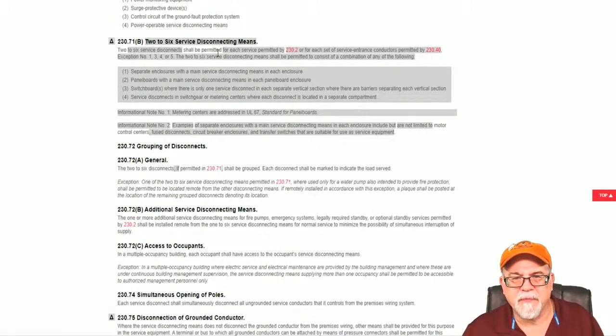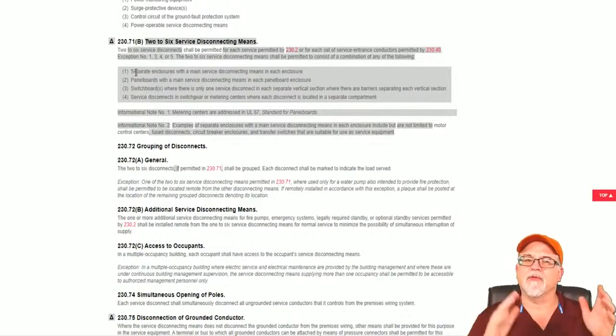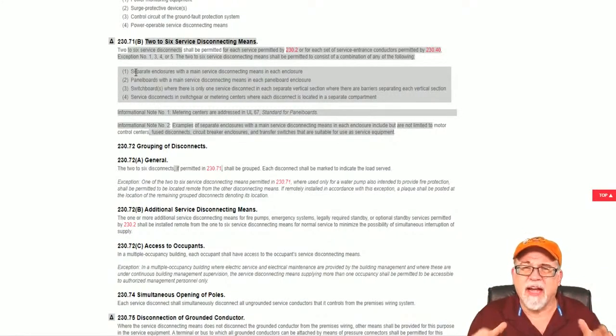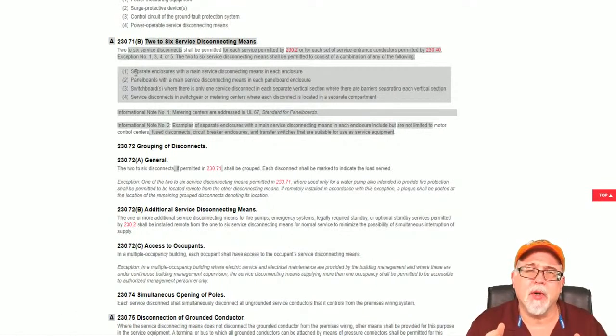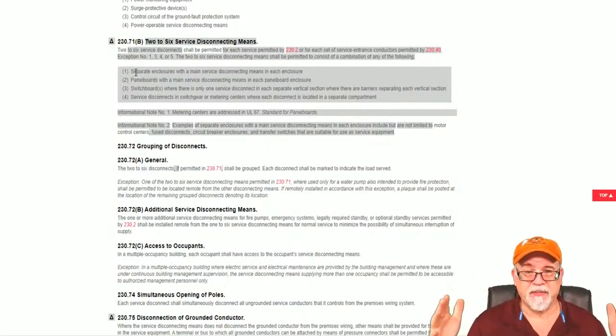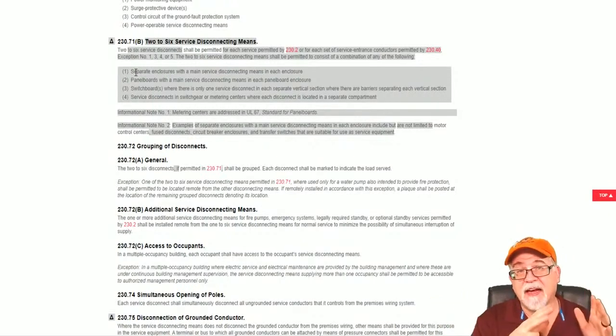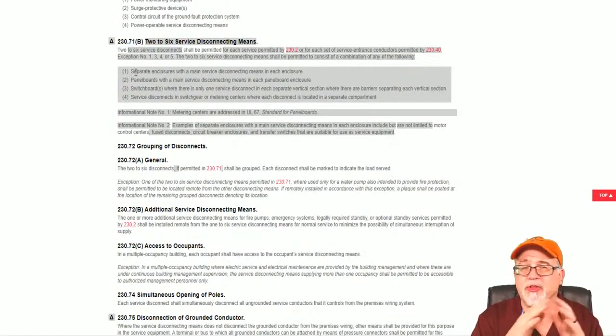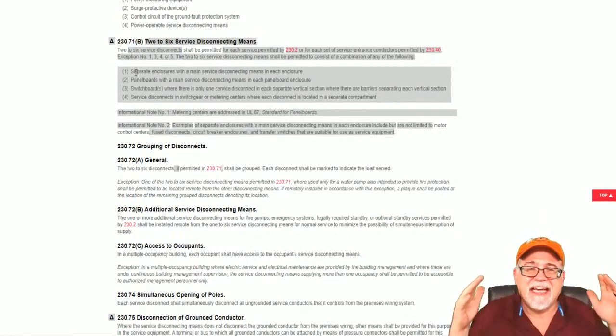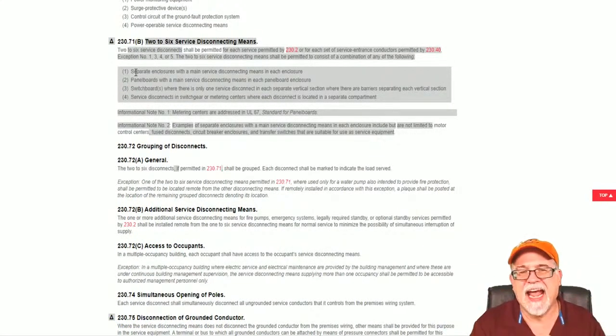You'll notice it says the 2 to 6 disconnecting shall be permitted in each service permitted by 230.2, for each service entrance conductor set in 230.40. Well, you no longer have the 6 disconnect rule where you can have 6 in a panel board, have 6 separate breakers. That's no longer there anymore, that's been removed for the 2020 code. You can have either one main breaker, or you could have 6 separate panels with a main disconnect, but you no longer can have 2, 3, 4, 5, or even 6 in the same panel enclosure. You can't have it anymore.